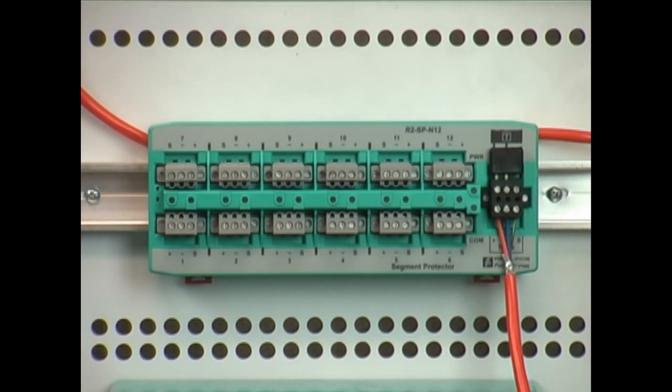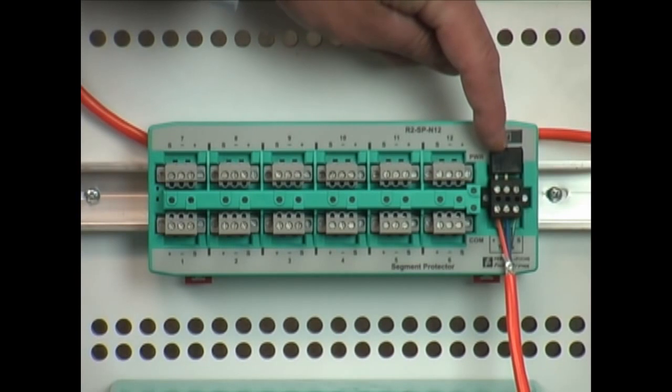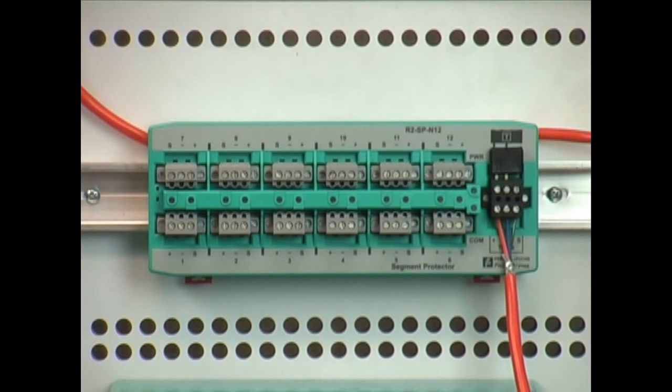Additionally built into the segment protector is the second terminator that you need for your foundation field bus segment. So again it's already included with the segment protector and makes it easier to ensure that you have two per segment.